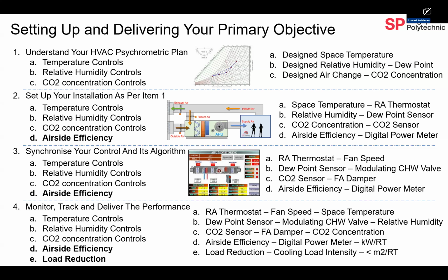One of the issues we always face is humidity, but we don't have humidity controls. This is one reason why we have high humidity and moldy issues, because our control is only based on temperature, while humidity is one of the objectives of your design but there's no control for it. Now we put in CO2 concentration and air change control, all integrated such that if there's a change in condition, they work automatically.